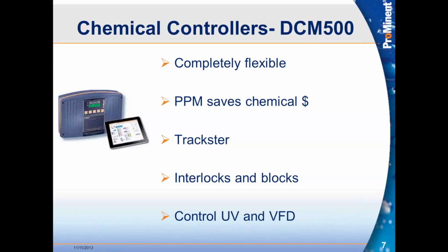Let me give you two really quick examples of doing an interlock. Instead of hardwiring some type of flow switch into a system as a redundant safety flow switch for preventing chemical feed when the flow in the system stops, we can take flow meter information into the DCM 500 series, and we have GPMs appearing on the screen. We can configure the program so that if the GPM goes below a certain level, we turn off the capability of the controller to pump chemical. So that acts as a redundant safety switch to the safety switch that's already built into our flow cell. That gives people peace of mind and gives us some more flexibility.